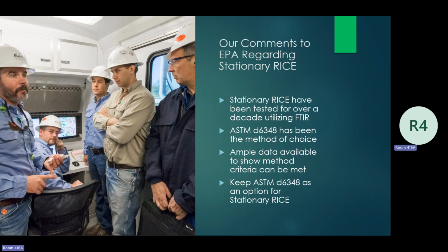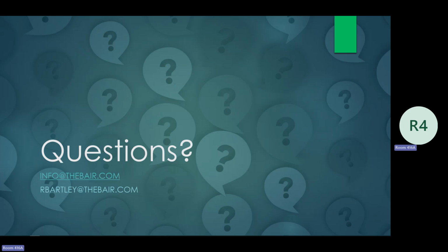The other source categories where you may be looking at other compounds that are difficult to sample for, that are challenging to get down to very low detection limits, that are challenging to ensure that they are transported through the system. Maybe Method 320 and the revisions apply to those better. But for stationary RICE, this is again the financial impacts, and then the reasoning behind making the method stricter. It just doesn't line up. We know that we can sample for these.